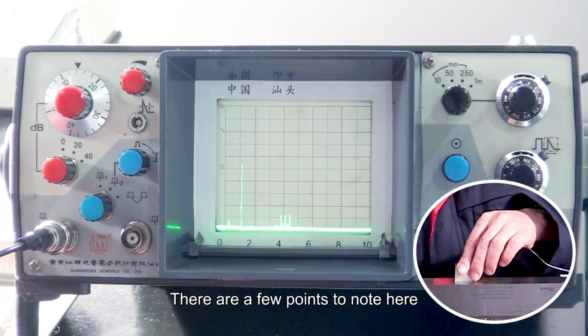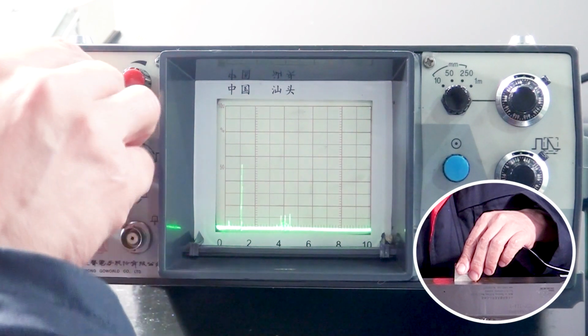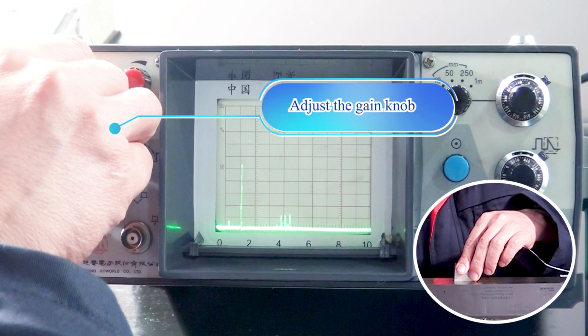There are a few points to note here. 1. Except that the gain knob can be adjusted when detecting the first cross hole, the gain knob cannot be adjusted again when detecting the remaining cross holes.